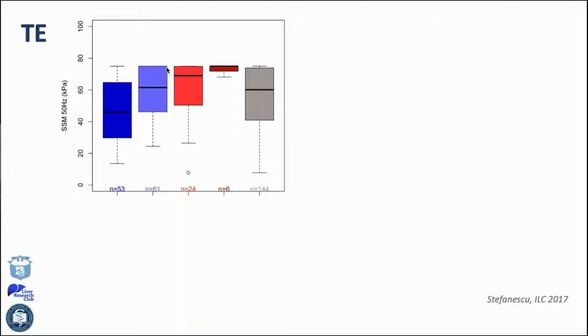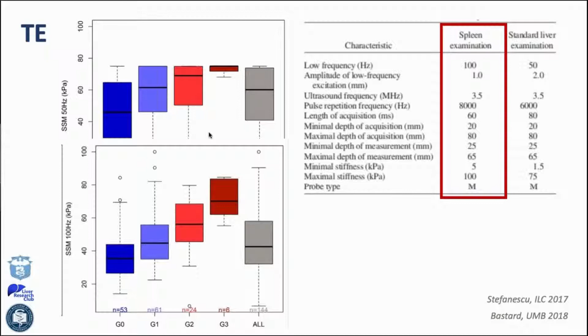Then an idea came to change the characteristic of the FibroScan probe. So the frequency of the mechanical vibration was changed. The depth of the measurement of the deformation of the tissue was changed. So an entirely new spleen probe was developed, and by using this probe, a much better differentiation was obtained. So this will be the new spleen FibroScan that will be soon available on the market, dedicated for spleen stiffness measurement.